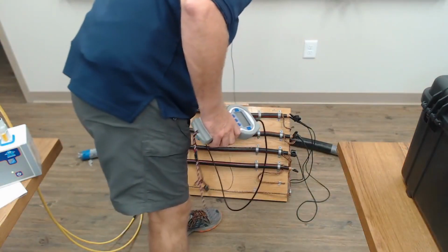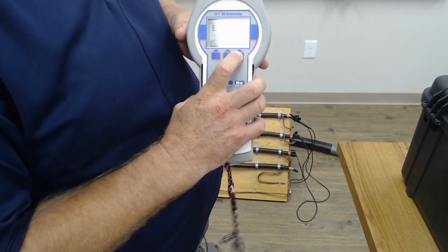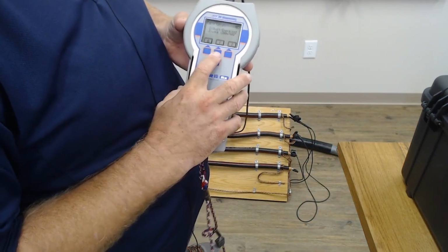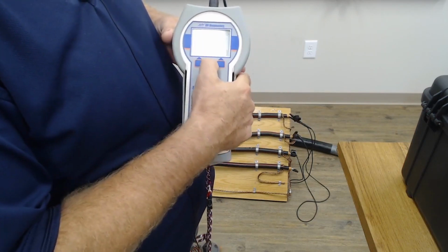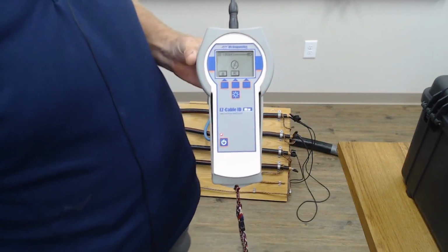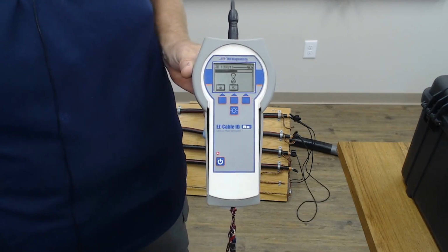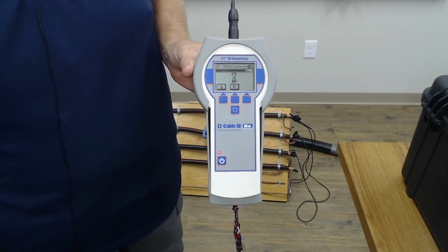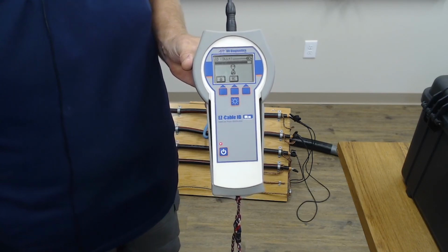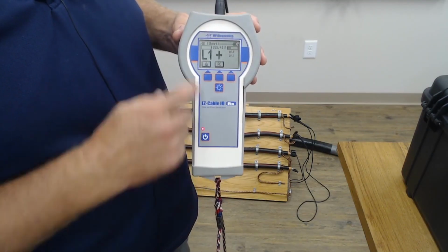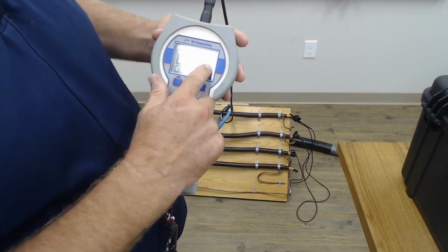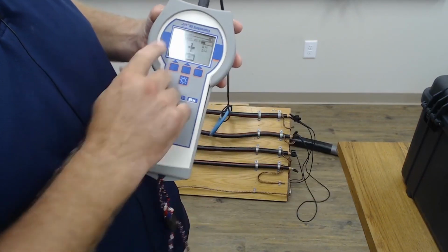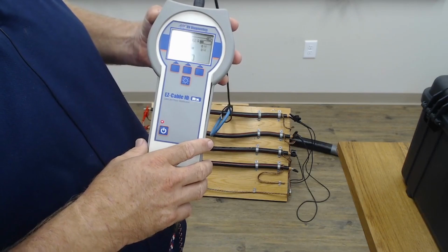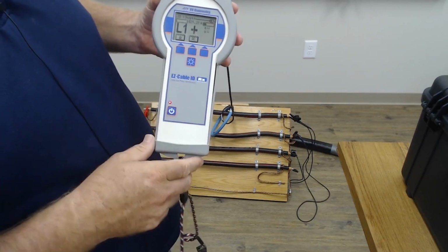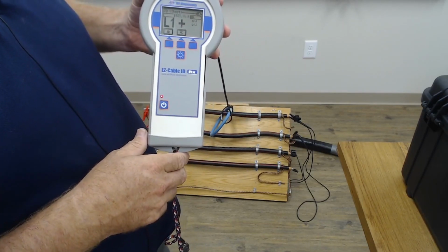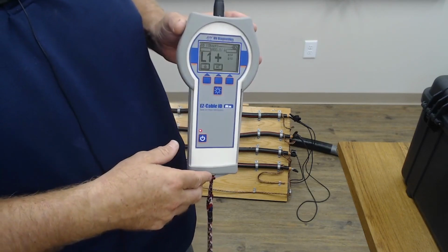And at this point, we want to find out what are we on? So we just say identify. Is this a short cable or a long cable? We're obviously on a short cable here right now. And then the unit should identify for us. And hopefully it will be L1. It's now looking for the signal, and there you have L1 positive, which means it's in the right direction, and it's L1, and you can see we have around about 33 amps that are being injected into that cable right now. About 30 amps. Let me get the reflection away.